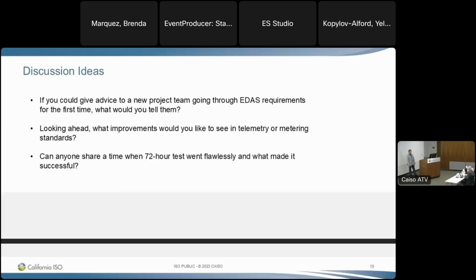If I can expand on the standards, I'd also like EDAS to take another look at the 0.3% accuracy for CTs. I think it needs to be more explicitly defined, because 0.3% accuracy for a CT that's oversized by a factor of 10 still meets the CAISO standard, and I'm having a hard time telling clients that they're way outside of their accuracy specification because I can't point to a standard that enforces that.